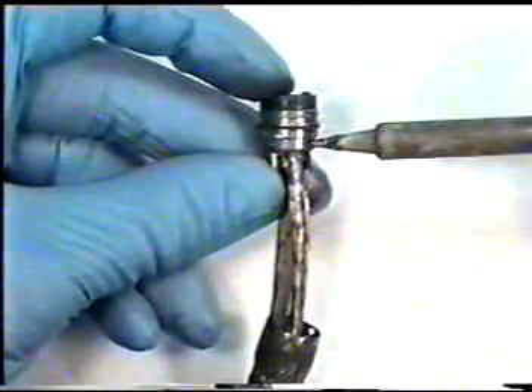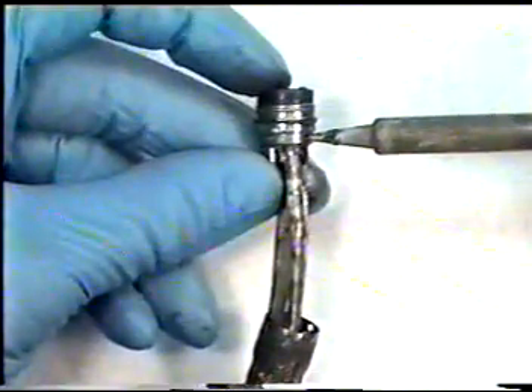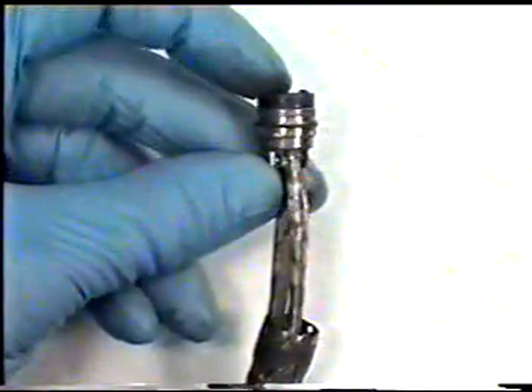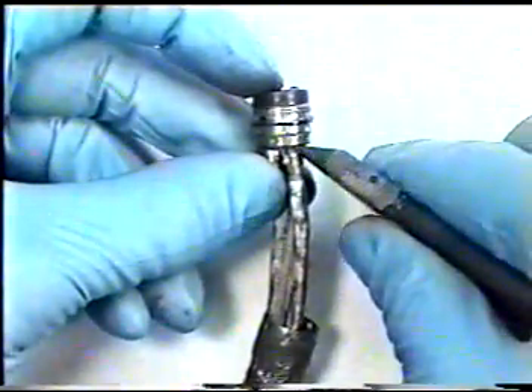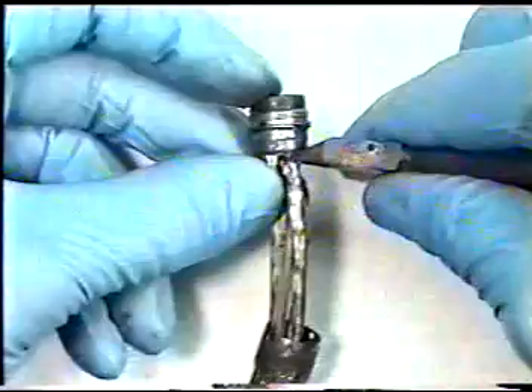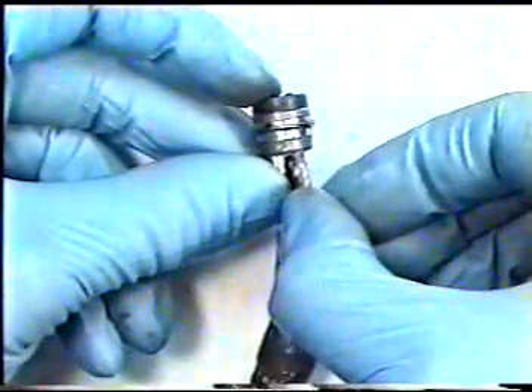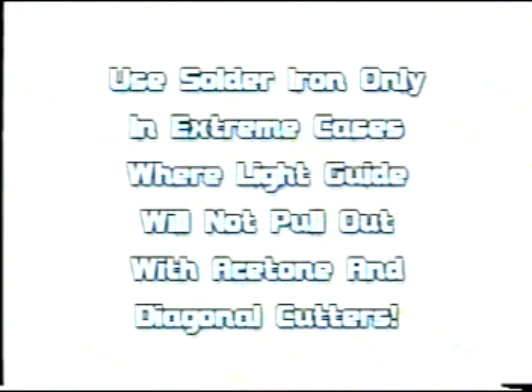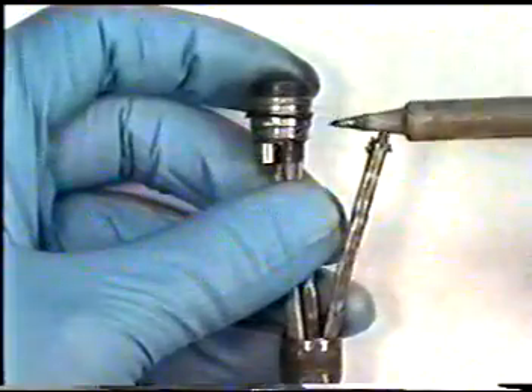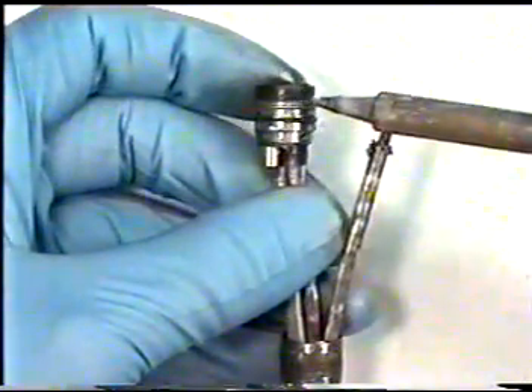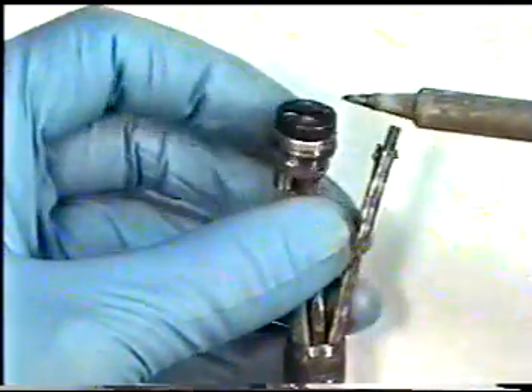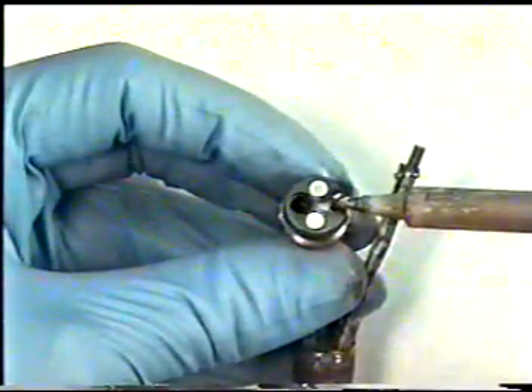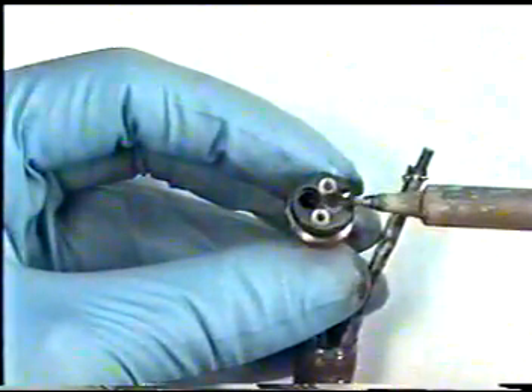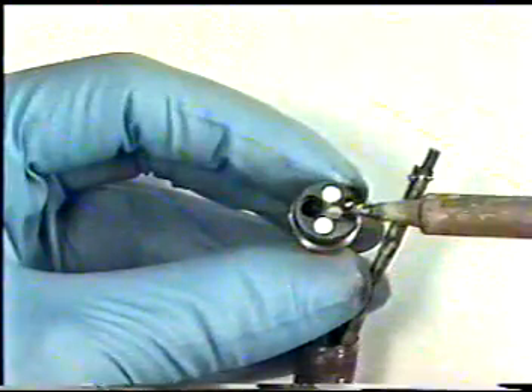Once the tip has heated up with your soldering iron, you'll need to quickly remove your soldering iron and, using your diagonal pliers, pry out the illumination light guide bundles. You must use your soldering iron very quickly, because if the distal tip is heated up too long, it may cause damage to your objective lens system, which will cause image guide problems with either a CCD chip or image guide fiberscope bundle.